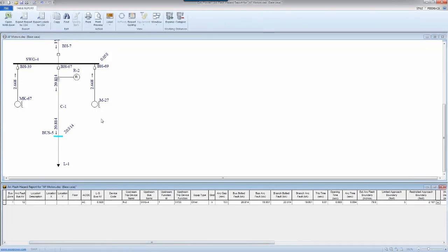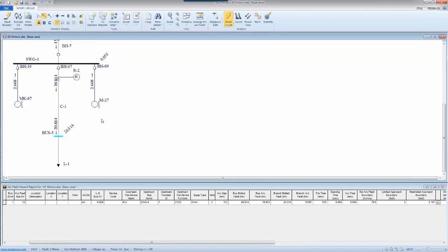So it started from time 0, went through iterations, 1st, 2nd, 3rd, 4th, and once it passed the first cycle, it updates the short circuit fault current values. It goes until the beginning of the 8th cycle. If we had gone beyond the 8th cycle, you would have seen the 30 cycle value here, which is not the case, because for that, the trip time should have been larger than the 8th cycle, which doesn't happen here. It's almost closer to the 6th cycle. So that's why for the integrated method, you see this value.